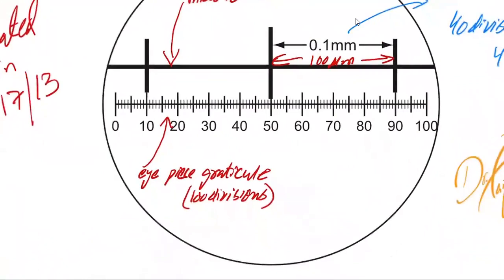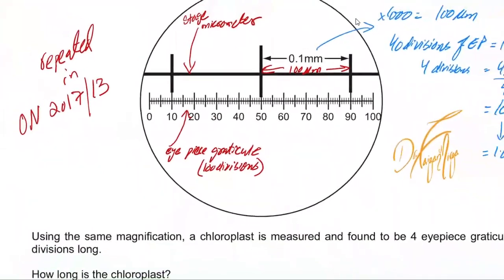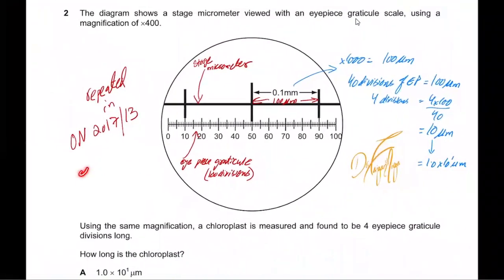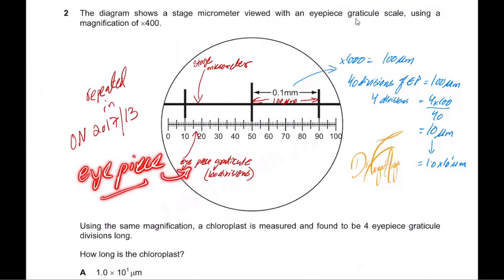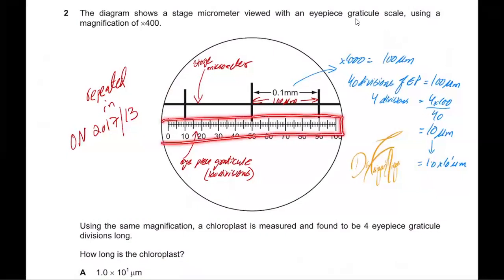An eyepiece graticule has 100 divisions and is fitted into the eyepiece of the microscope. When using a light microscope, you fit this eyepiece graticule — it's a circular glass slide with a scale etched on it — into the IPS, and then insert that eyepiece back into the light microscope. When you view the specimen placed on the stage, this scale will be seen on top of that specimen.